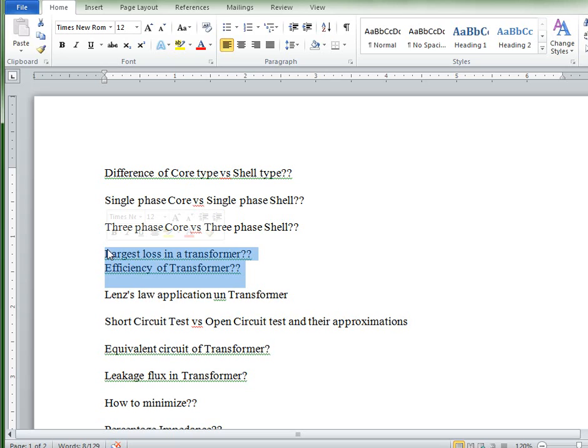The largest loss in a transformer is copper loss. But the same transformer, when it is designed for a generating station, something at Tarbela or Mangla, you are not going to have its copper losses under consideration. You are only going to see that this much loss should be minimum, because it's going to run for only 8 or 10 hours. So the design is very important, that is, which is the loss.